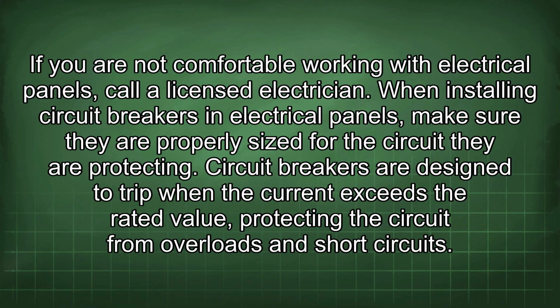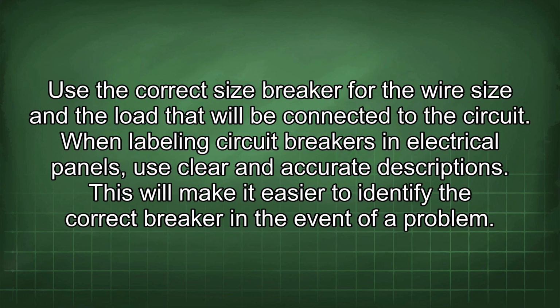When installing circuit breakers in electrical panels, make sure they are properly sized for the circuit they are protecting. Circuit breakers are designed to trip when the current exceeds the rated value, protecting the circuit from overloads and short circuits. Use the correct size breaker for the wire size and the load that will be connected to the circuit.